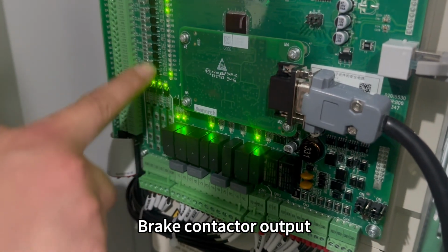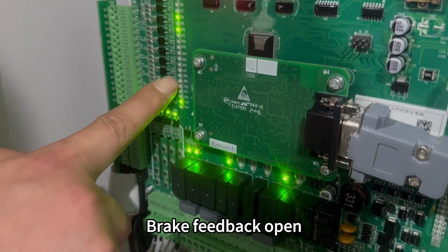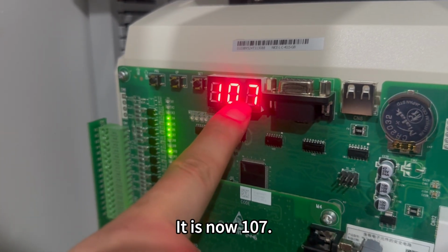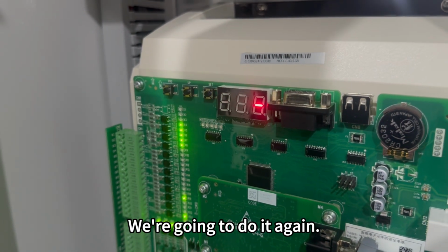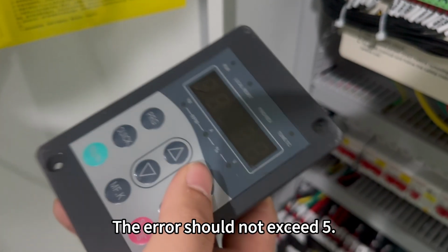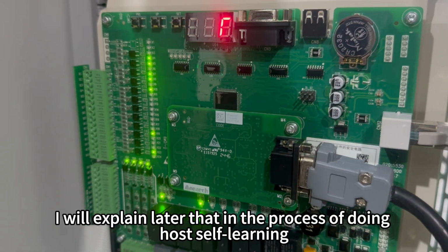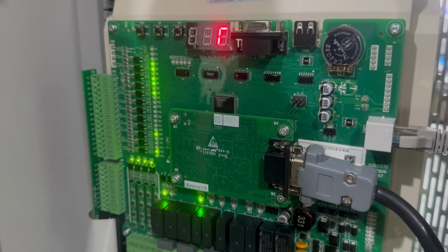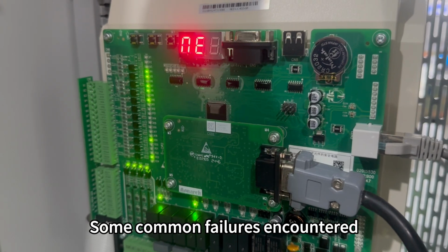Brake contactor output, then the brake switch. Brake feedback open. It is now 107. It's over 5. We're going to do it again. The error should not exceed 5. I will explain later some common failures encountered in the process of doing host self-learning.